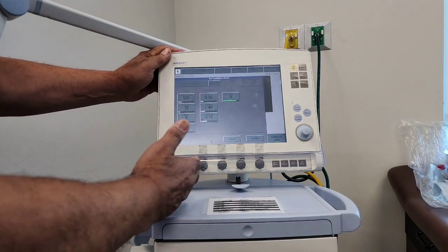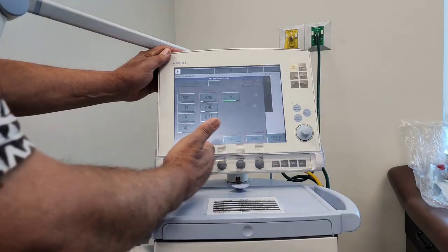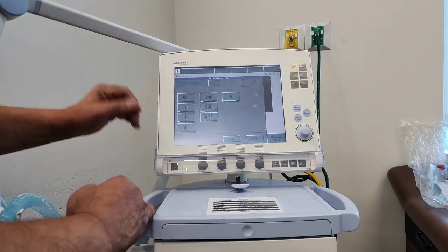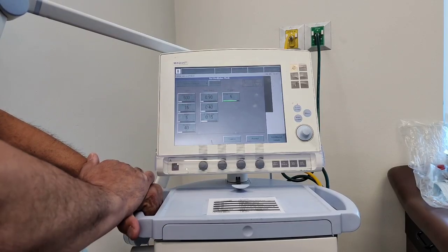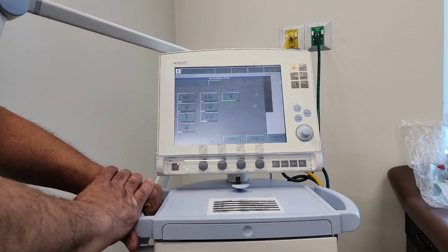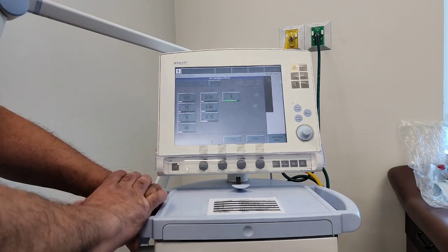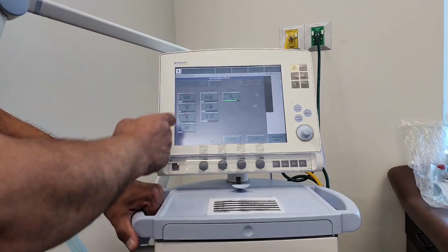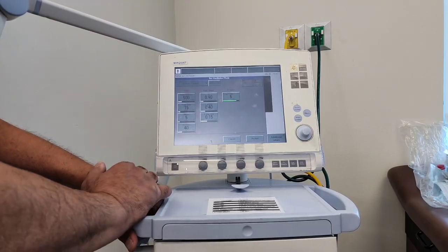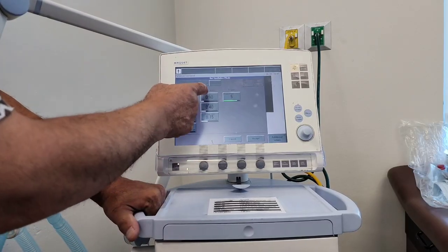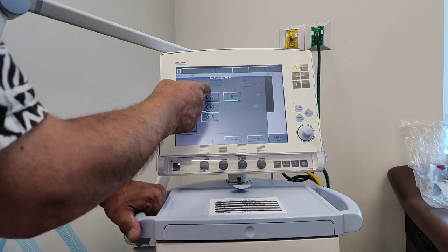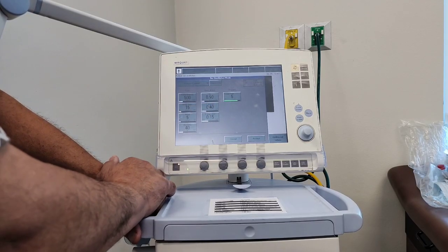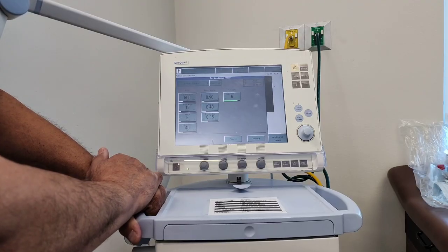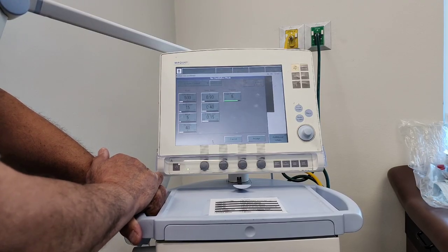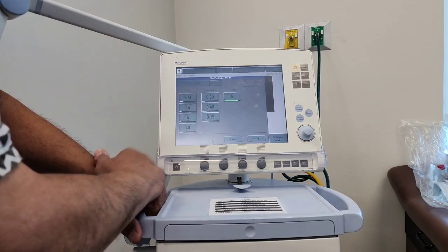So I'm going to go into volume control. You can tap up there, and it'll basically show everything that was down here on the bottom right in here. It will show you your tidal volume, how much we want to give the patient, and that we're going to get with ideal body weight, and we'll talk all about that. Respiratory rate, your PEEP, your oxygen concentration, and then there's some things here that we can adjust, and we'll learn about them. The I time, how long we want the inspiratory phase to take. Right now it's set to 0.9 seconds.